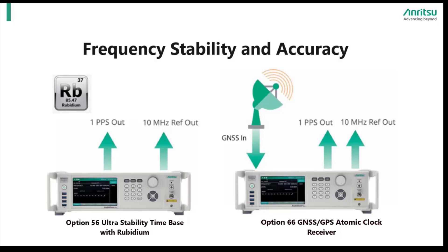It is also useful in situations where a satellite signal is inaccessible for any reason. For customers that can access a GPS GNSS signal and require atomic clock accuracy, such as metrology calibration labs and others, Option 66 is the beneficial choice.